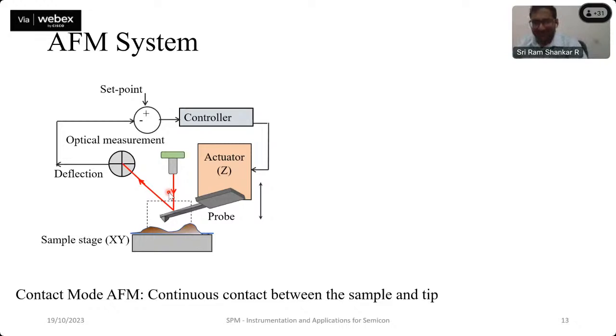Okay, so this is the simplest schematic that we can come up with for an AFM system. And the simplest technique with which we can use such a system is called contact mode AFM, wherein you maintain continuous contact with the sample and the tip.